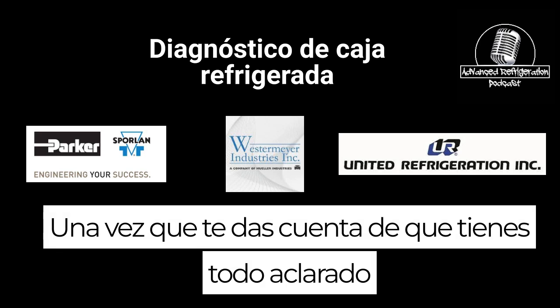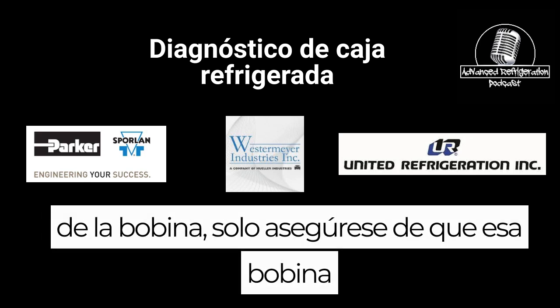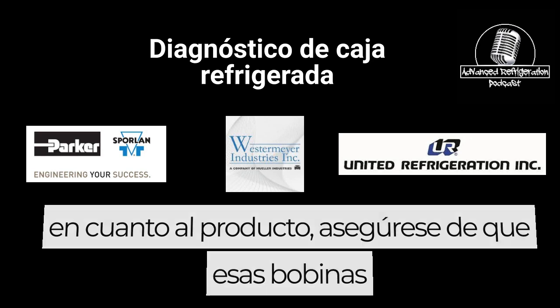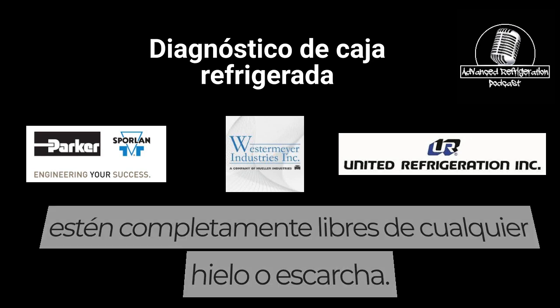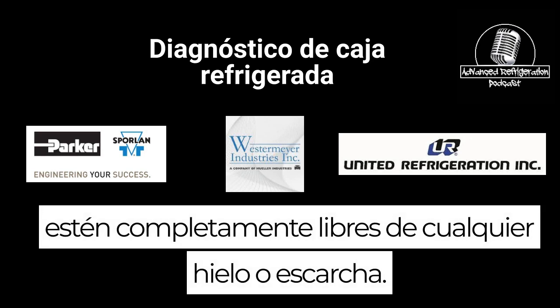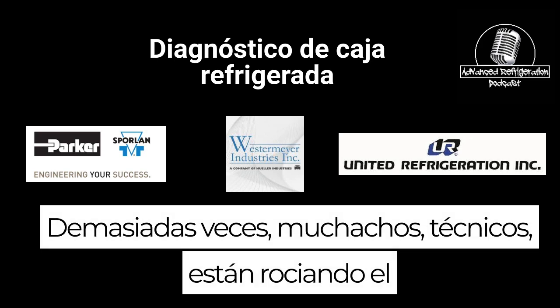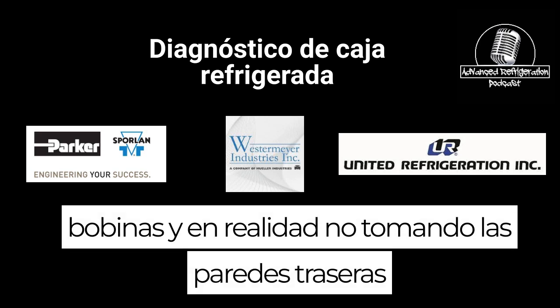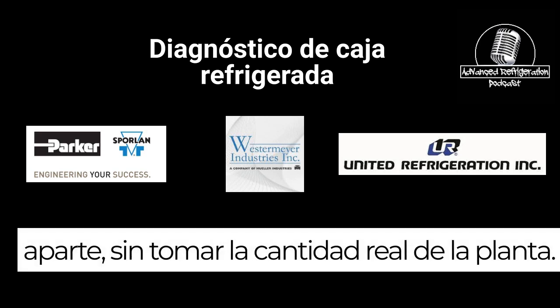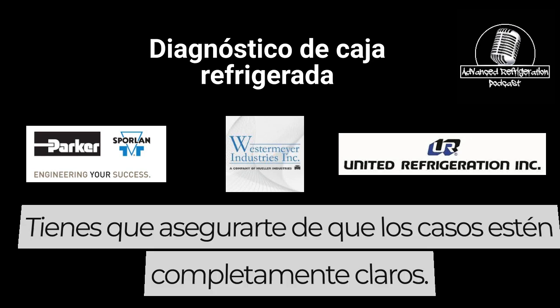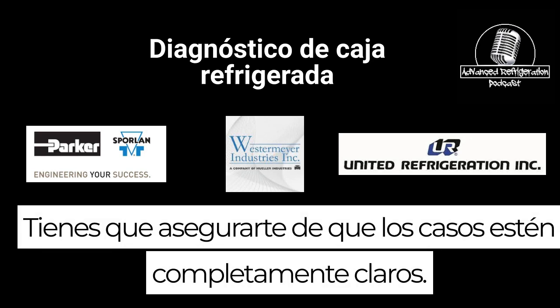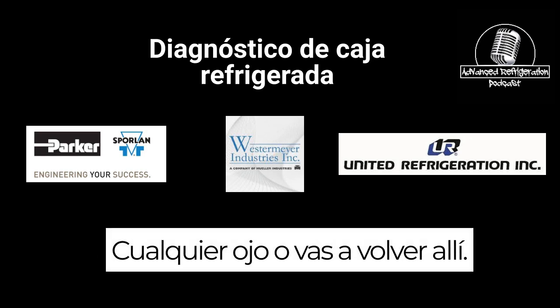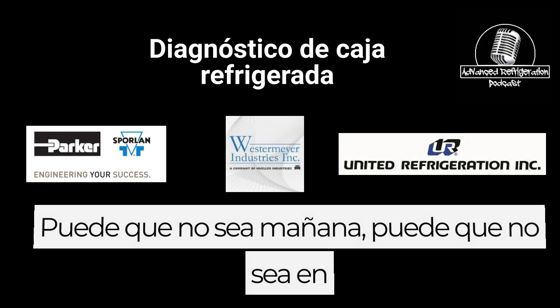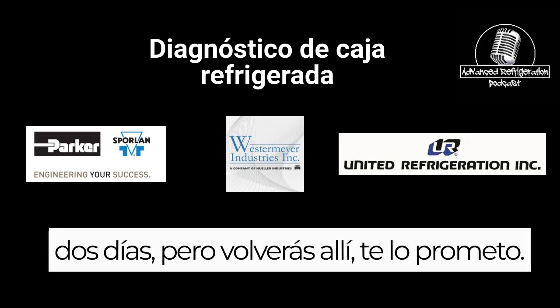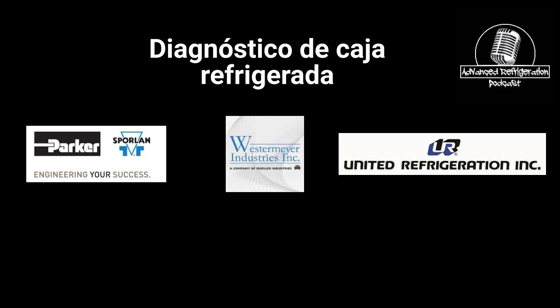Once you've figured that you got everything cleared out of the coil, make sure those coils are completely clear of any ice or frost. Too many times, technicians are spraying the coils and not actually taking the back walls apart, not taking the actual plenum out. You have to make sure the cases are fully clear of any ice, or you're going to be back there. It may not be tomorrow, may not be in 2 days, but you'll be back there. I promise you.